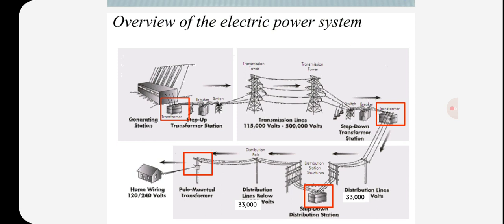At the generating station, the voltage of 6.6 or 11 or 33 kV is stepped up to 132 kV or 220 kV or 400 kV or 765 kV with the help of step up transformers for transmission, and then stepped down to 66 kV or 33 kV or 11 kV at various substations with the help of step down transformers, and further stepped down to 400 by 230 volts by means of distribution transformers for consumers.